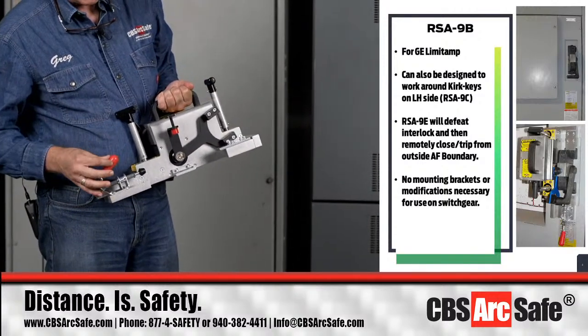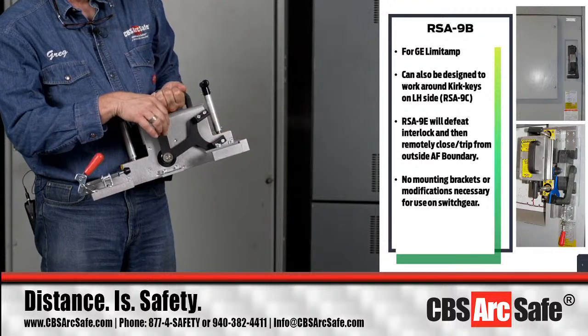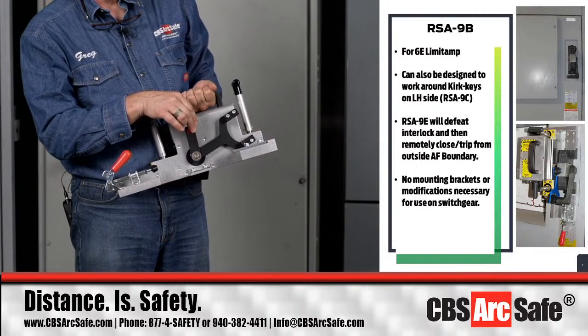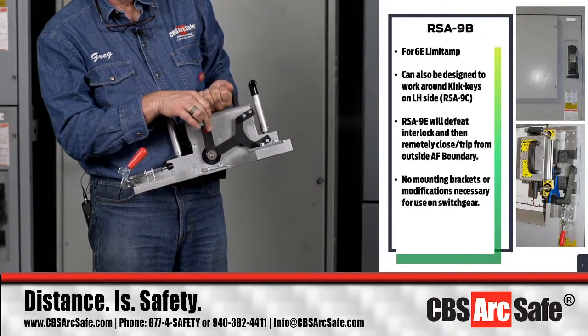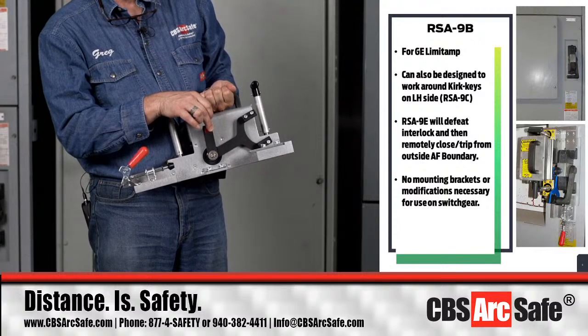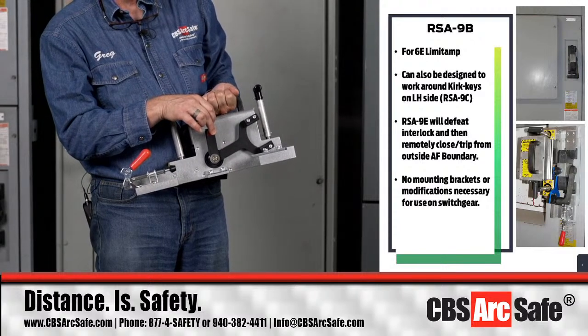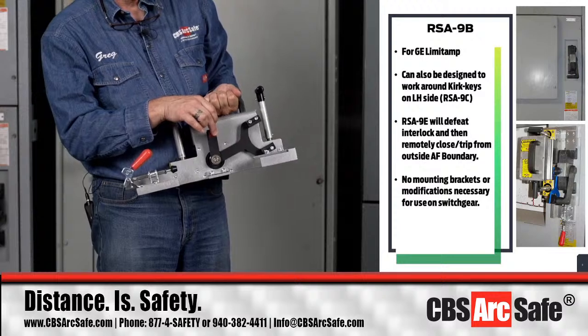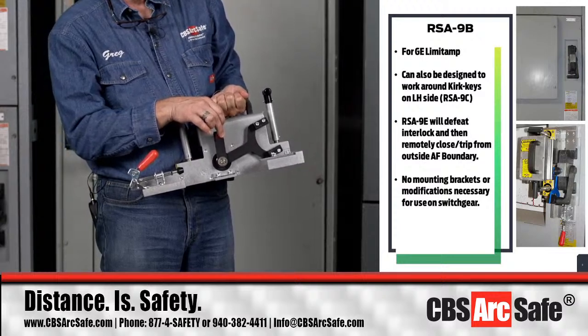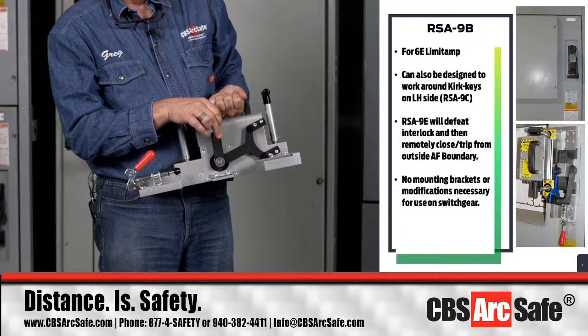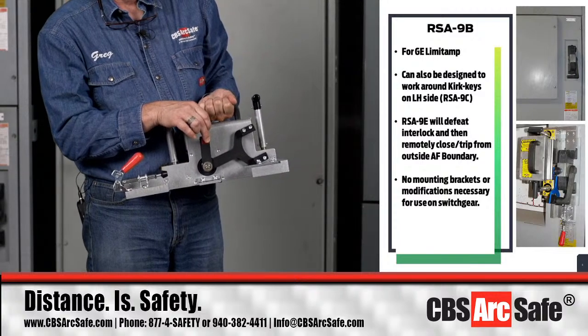It's got one more position lock down here at the bottom. This is the interlock defeat for pushing in the hand defeat that you have to be able to actuate the handle. A couple things to note: we have the RSA-9C and the RSA-9E, which actually will defeat this electronically and then allow you to actuate it. So we have a couple different versions depending upon what you want.